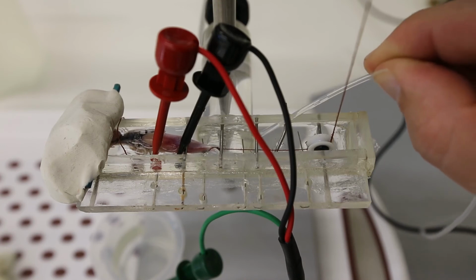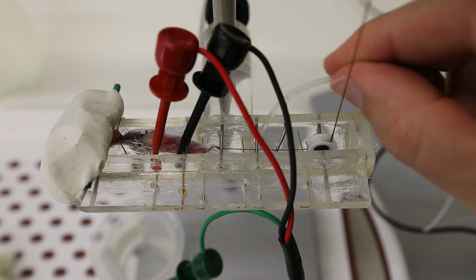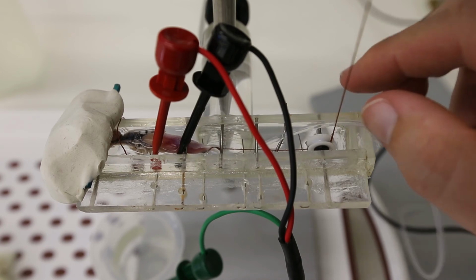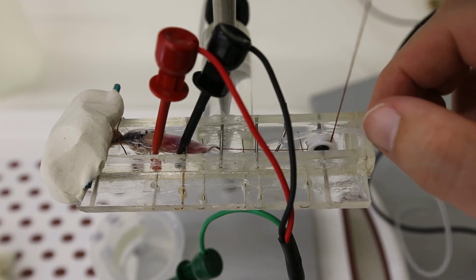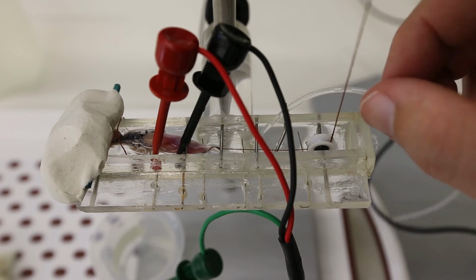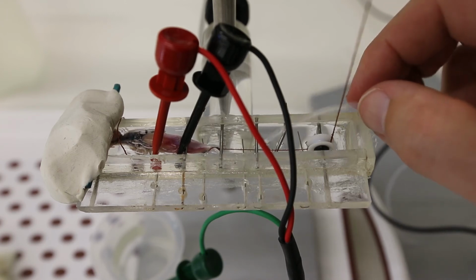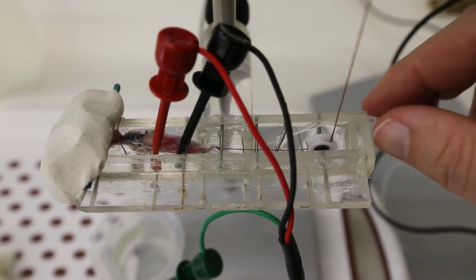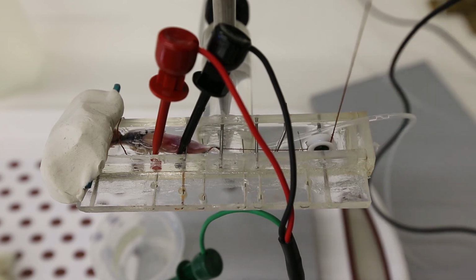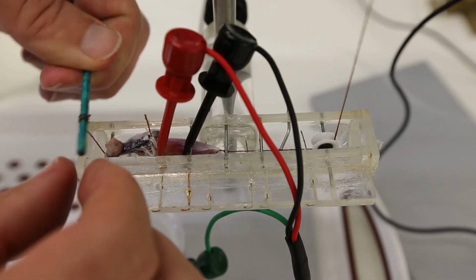Lastly, we need to add the oxygen tubing to the tissue bath. You can either add the oxygen tubing from the pulley end or from the plasticine end of the tissue bath. If you add the tubing from the pulley end, you can often slide the tubing underneath the metal bars or the unused electrodes. With the tubing in place, adjust the flow of oxygen so that you get a steady but gentle stream of bubbles. If the oxygen bubbles are too rough, they will cause the solution to splash everywhere and will also disrupt the force readings of your muscle.